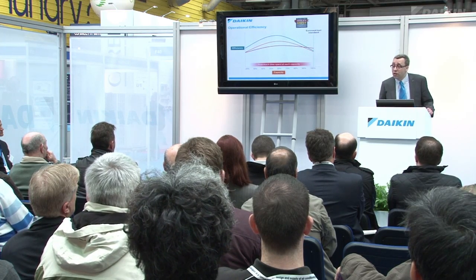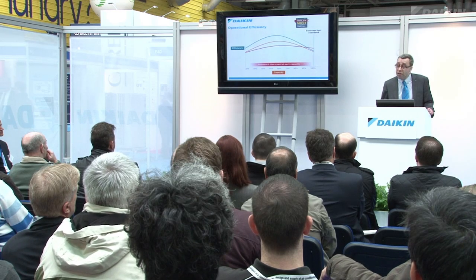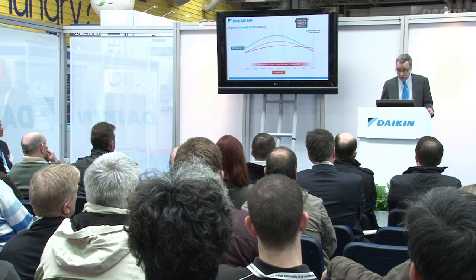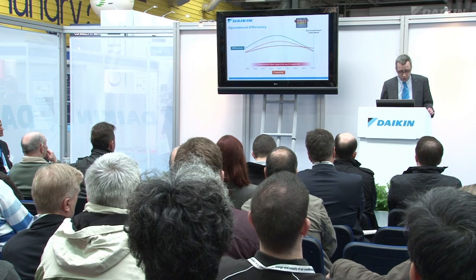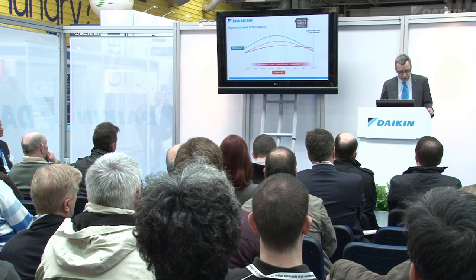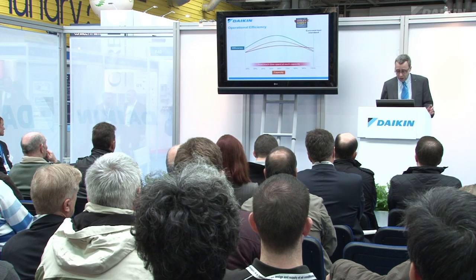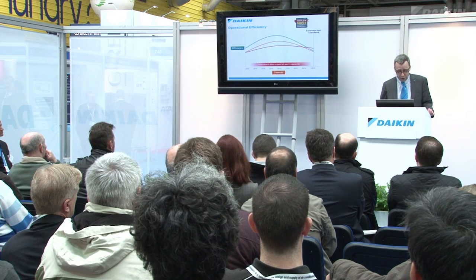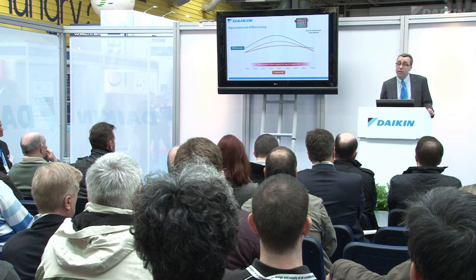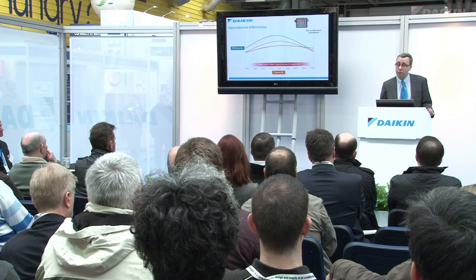So today, Daikin will be revealing VRV Heat Recovery System version 4 into the market. And remember, at the beginning when I mentioned how much it had changed from a performance point of view, that we no longer just vary the amount of refrigerant going through the system, we're also varying the evaporating and condensing temperatures throughout the system. So I'm very proud to announce that we will be bringing variable refrigerant temperature to Heat Recovery VRV. In order to show you how it all works, it will take quite some time. So instead, I'm going to show you what it does.